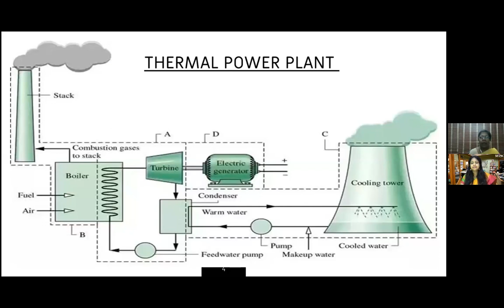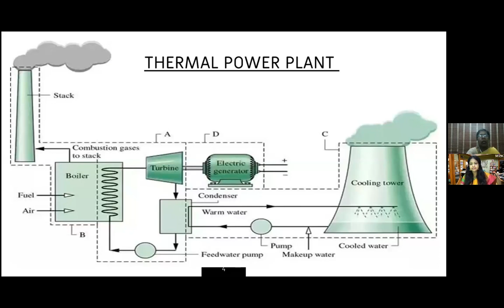We have a number of variables in one stage of the power plant. In a boiler itself, we have a number of variables, so I have to go for a number of control loops, one for each and every variable. In the power plant you have different stages, and each stage has a number of variables. All the variables must be maintained constant to have good efficiency from a thermal power plant. If I implement this, I can say the thermal power plant is completely automated. This is what we call process automation. I think it is clear to the audience what process automation is.